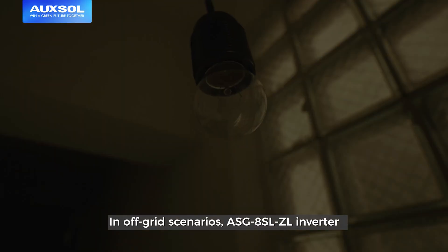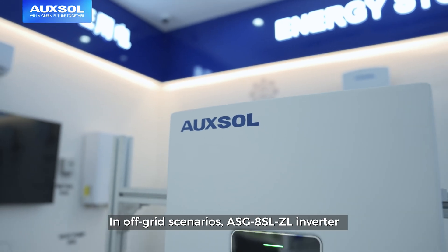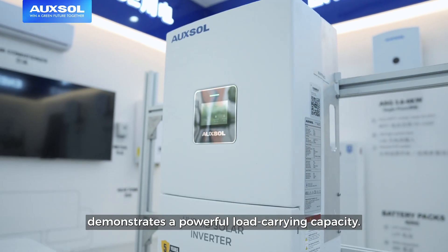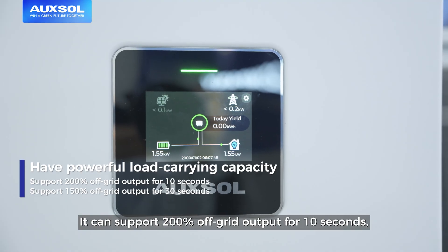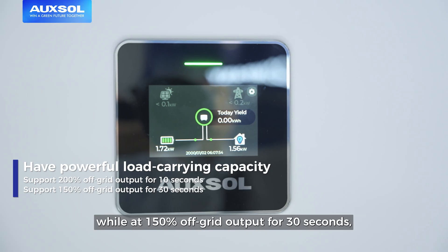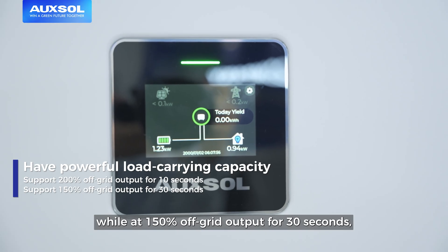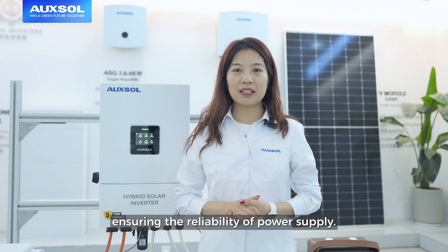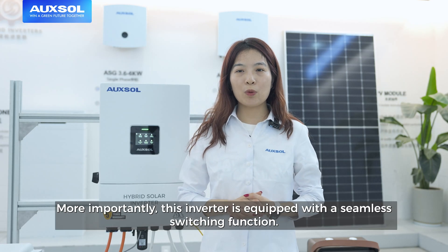In off-grid scenarios, the ASG-8SL-ZL inverter demonstrates a powerful load carrying capacity. It can support 200% off-grid output for 10 seconds while at 150% off-grid output for 30 seconds, ensuring the reliability of power supply.